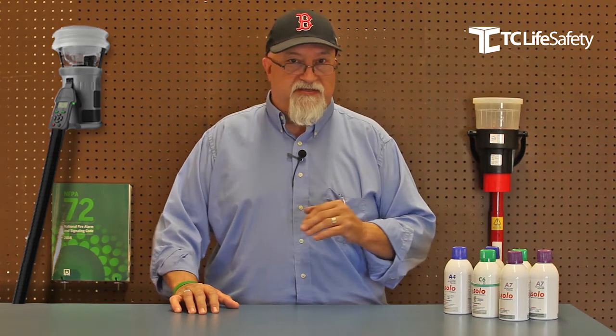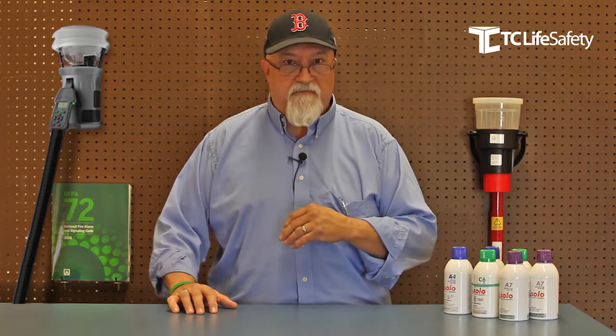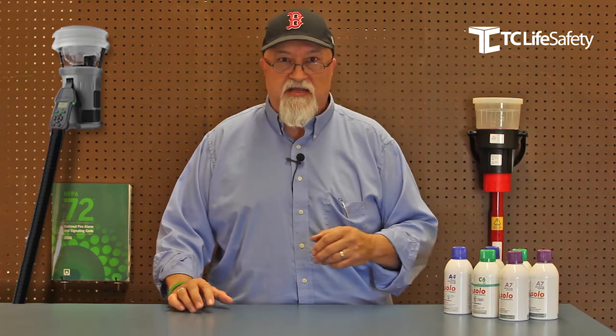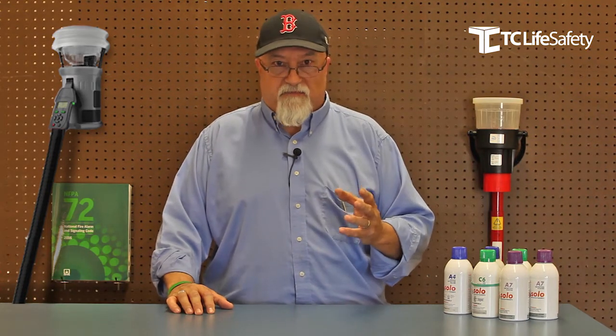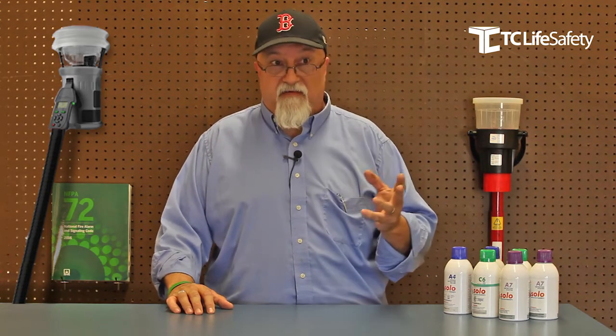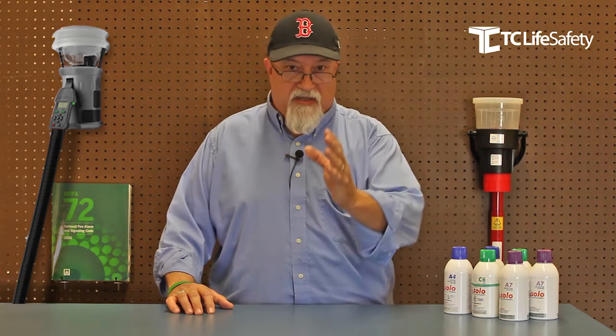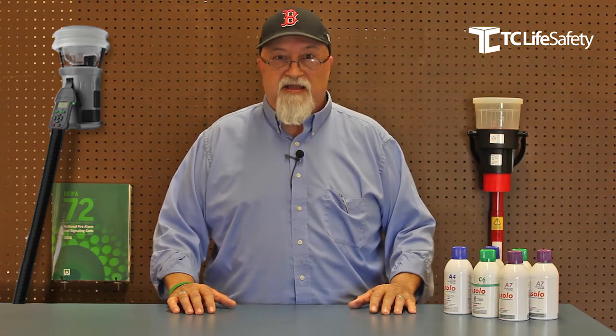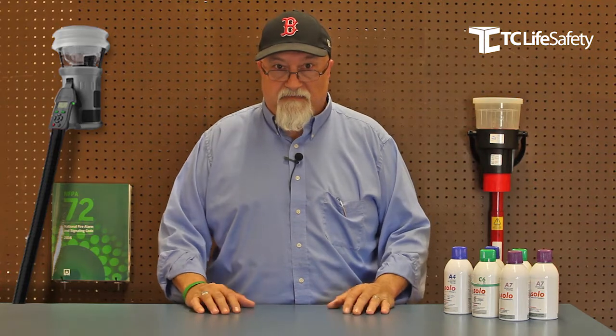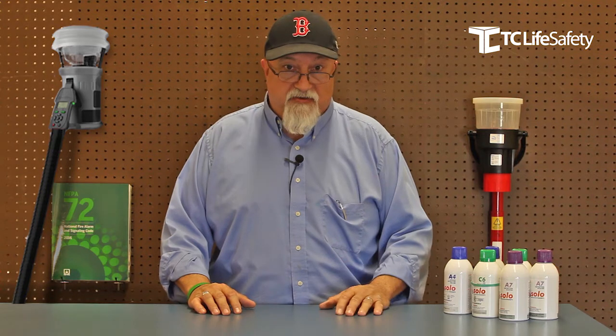Today the technology is just going rampant — it's hard to keep up. The data acquisition is quick and easy. With the new analog addressable systems, we're able to go in and get sensitivity testing. All we do is push a button on the keyboard and we can get out a complete listing of all the analog addressable smoke detectors and their current sensitivity. It's listed for the purpose and accepted by most authorities having jurisdiction.